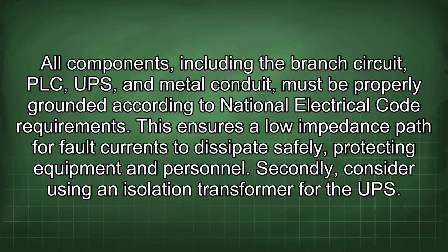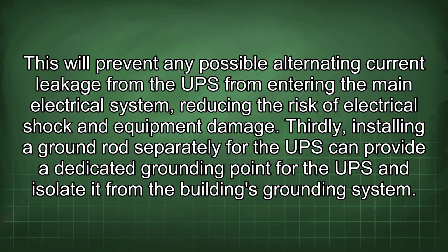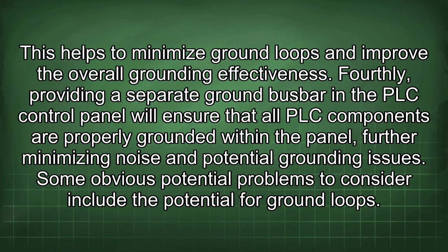Secondly, consider using an isolation transformer for the UPS. This will prevent any possible alternating current leakage from the UPS from entering the main electrical system, reducing the risk of electrical shock and equipment damage. Thirdly, installing a ground rod separately for the UPS can provide a dedicated grounding point for the UPS and isolate it from the building's grounding system. This helps to minimize ground loops and improve the overall grounding effectiveness. Fourthly, providing a separate ground busbar in the PLC control panel will ensure that all PLC components are properly grounded within the panel, further minimizing noise and potential grounding issues.